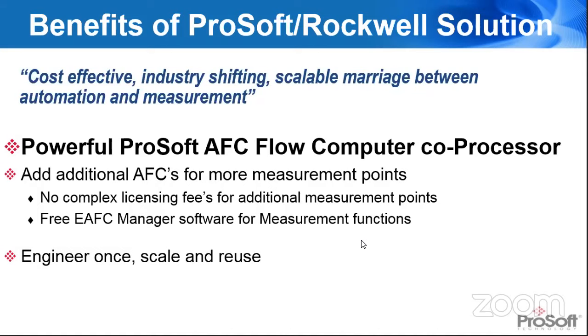One other thing, as we've worked with customers, measurement has some particular functions that they require. They need to be able to calibrate transmitters, enter orifice plate changes, and enter new meter factors as they prove Coriolis meters.